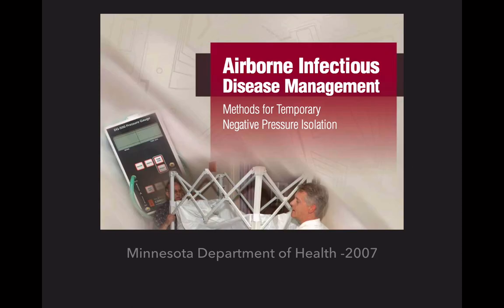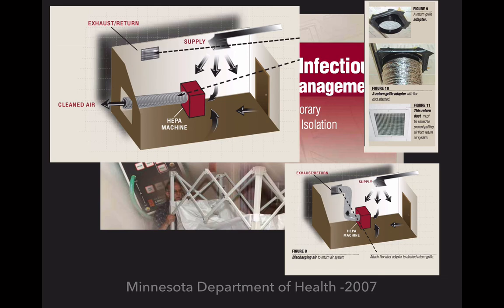Now, it gets even better though, because if you look at the Minnesota Department of Health, they actually have a booklet that's basically an IKEA instruction manual on how to convert any room, whether they have a window or not, into a negative pressure isolation room using a HEPA filter jerry-rigged onto an HVAC system, like a regular air conditioning system, right? So that might be something that you might need to consider if you don't have enough negative pressure isolation rooms, that you can actually convert rooms.